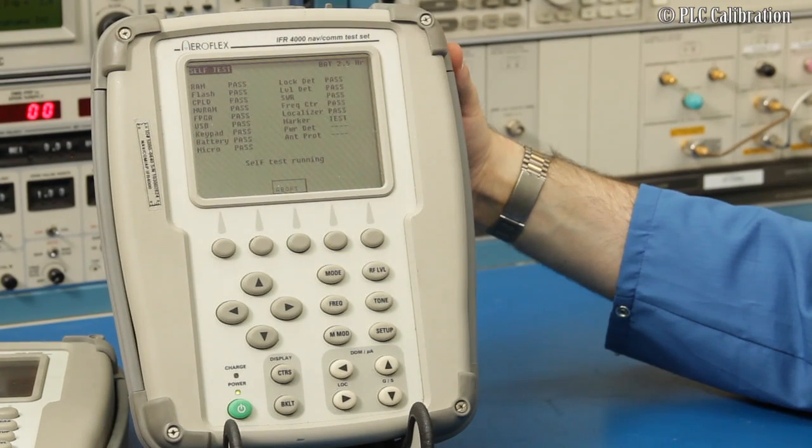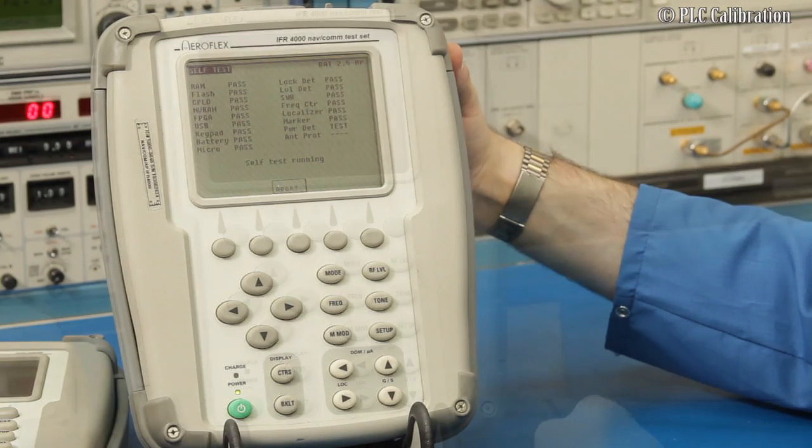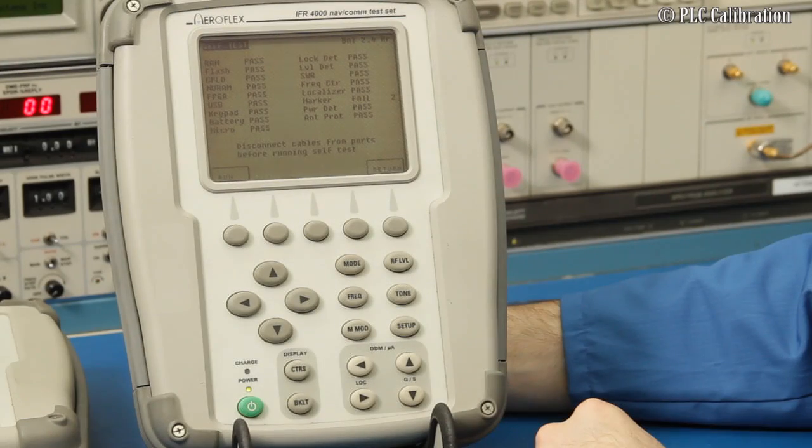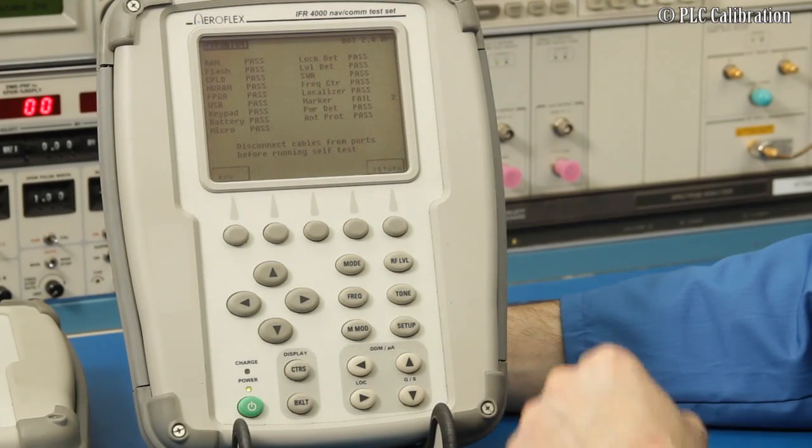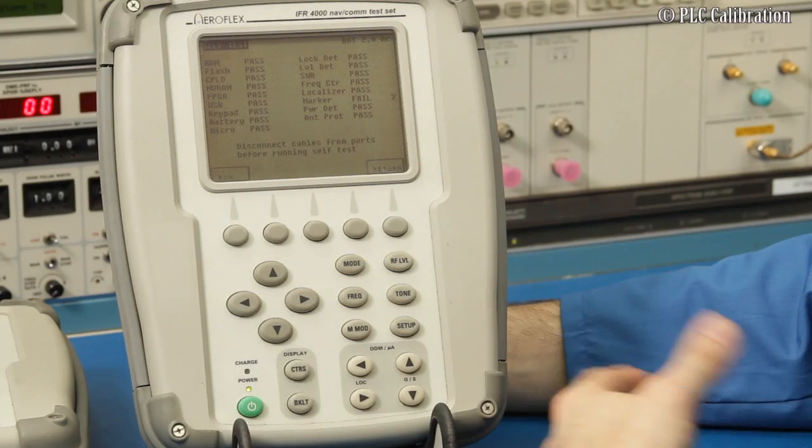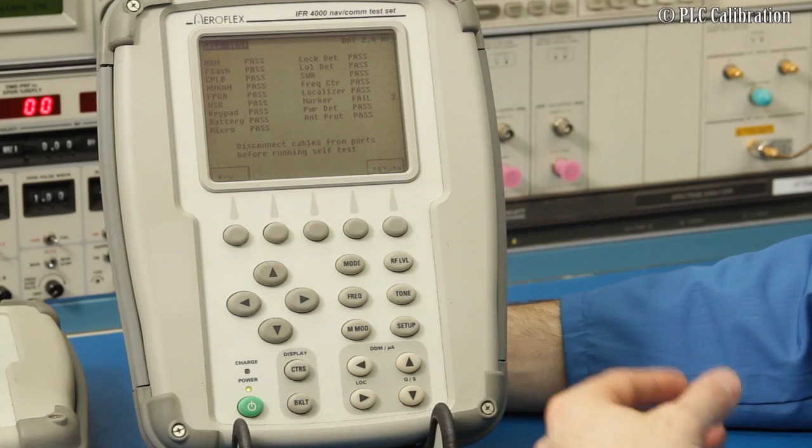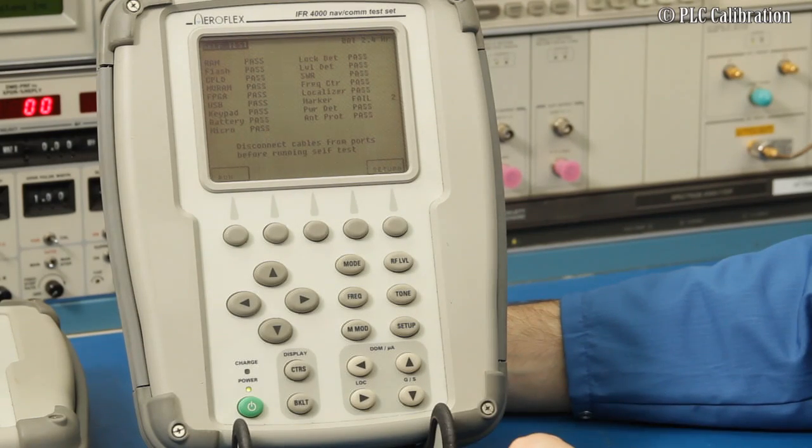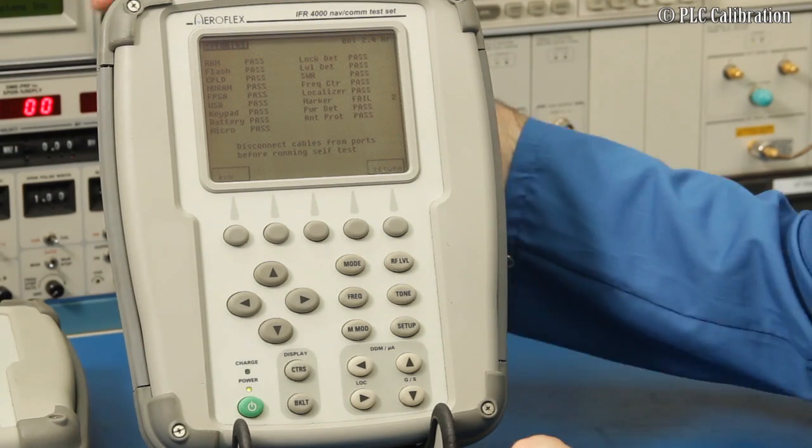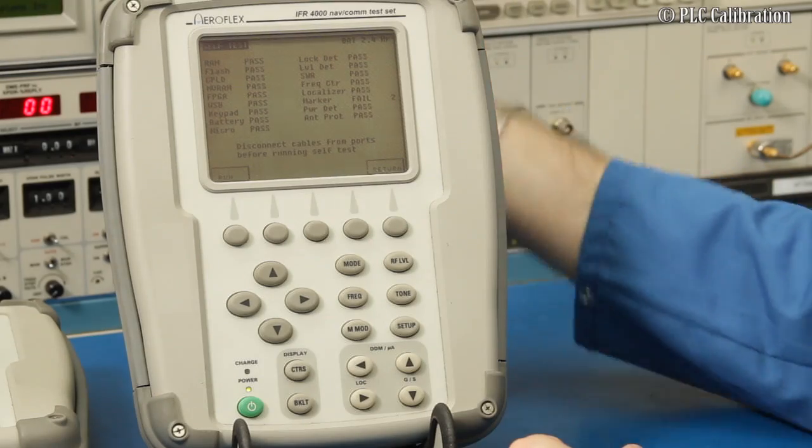And you can see that they're all almost finished here. Other things that you should know about on the self-test is when you start up, if you start up the unit too quickly and you go right into the self-test, it'll say it hasn't warmed up. So you just need to wait 30 seconds and then you can run the self-test again. Just make sure you have all the connectors unplugged.